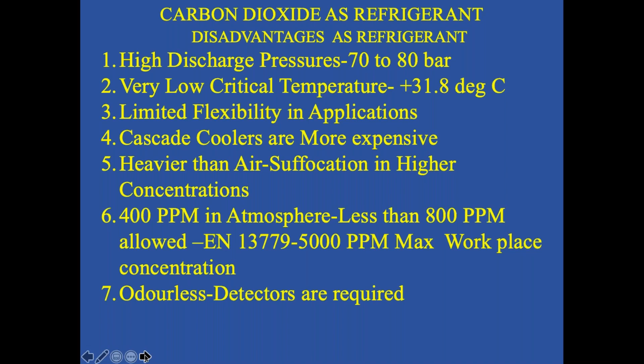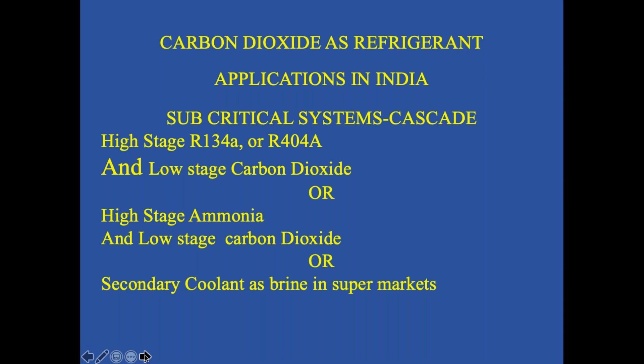So carbon dioxide as a refrigerant, what are the applications where we can use it in India? We can use it for high stage R134A, 404A, which we are already using, and for low stage, we can use carbon dioxide. Or alternately, I would suggest high stage ammonia and low stage carbon dioxide. This is a very, very popular application all over Europe and USA, especially for supermarkets. The ammonia plant is remotely located, and all your supermarket equipment with carbon dioxide is circulated as a secondary refrigerant. Or you can use secondary coolant as a brine in supermarkets, as I mentioned.